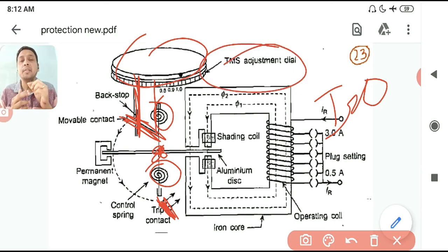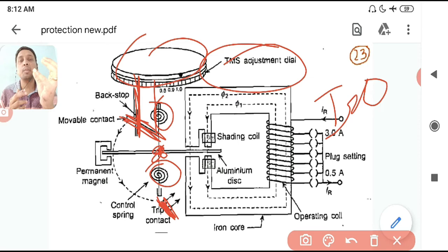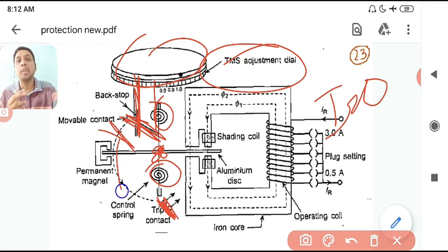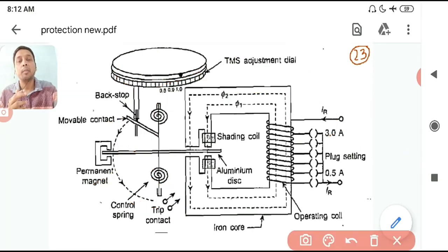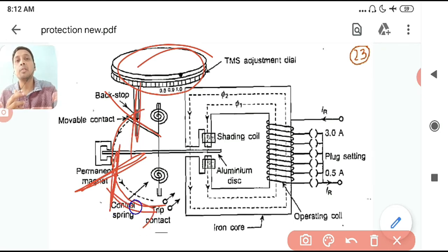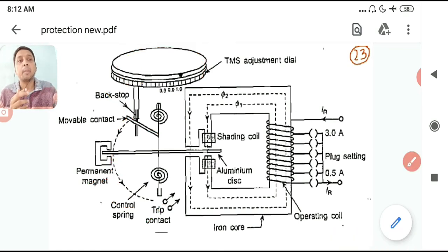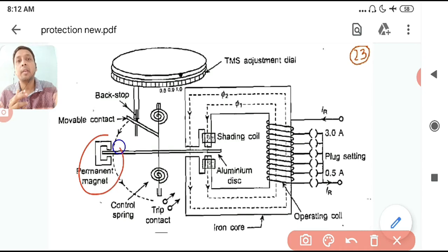If TMS is 1, the disc takes a full rotation — that is one TMS. If TMS is 0.6, the disc advances only 60% and starts from there. If it is 50%, the backstop is set so the disc starts from 50% of the rotation, taking much less time to trip. This is your time multiplier setting — TMS.